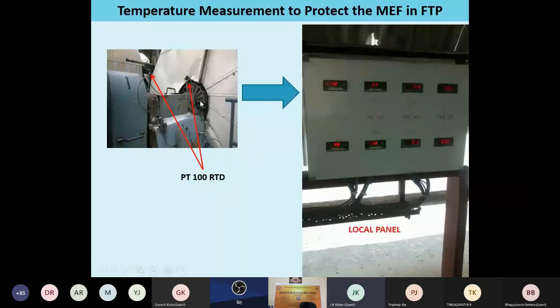This was a very old panel we have. Now in the new system this panel is not coming. We are feeding directly, the RTD card is inside the PLC, directly these cards take RTD signals. There are 3 wires on the RTDs. The 3 wires can be connected to the RTD card of the PLC, the RTD input card. But previously we had an old system that was just a temperature indicator controller. This signal is coming to this panel. Then it shows local indication, because it is situated locally, at the field. And then here there are contact points. These contact points will go to the PLC digital input card.